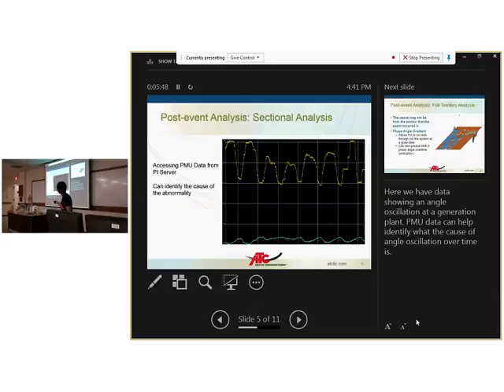And this is the conclusion I reached here: it's being caused by the generator nearby. Because there's only one generator nearby supplying the voltage and power, it has to have a large angle difference in order to have the power transfer over, whereas if there were more power generators along the way, then it wouldn't be so large.